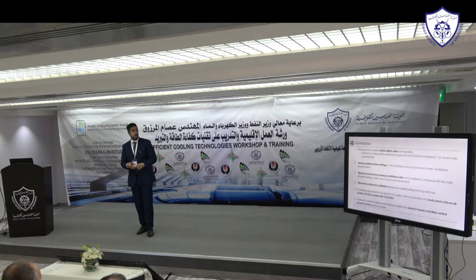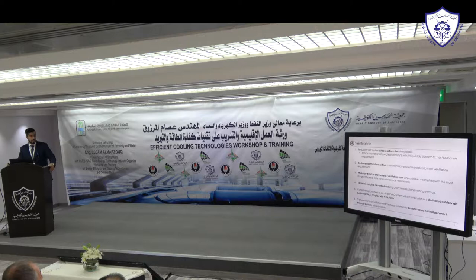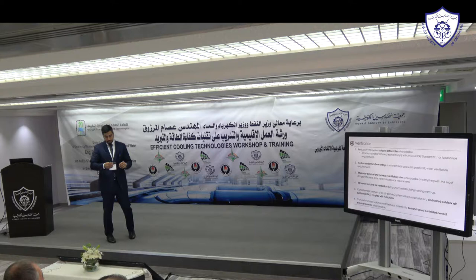You can check the amount of fresh air you have, compare it to code requirements, and try to reduce that amount — because the more air that comes into the building, the more energy you need to cool it down and dehumidify it. Some buildings following LEED requirements may have ventilation rates 30% higher than code, so you need to be careful about what you're trying to achieve.